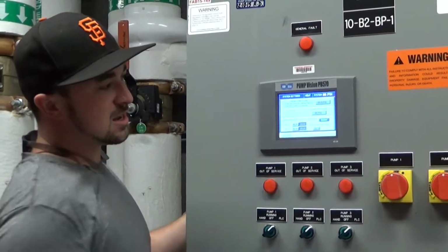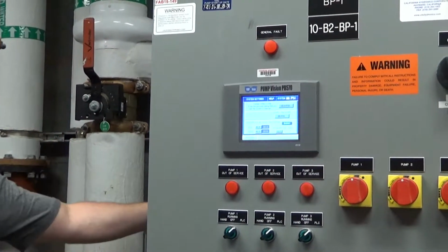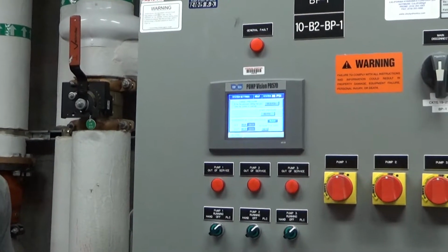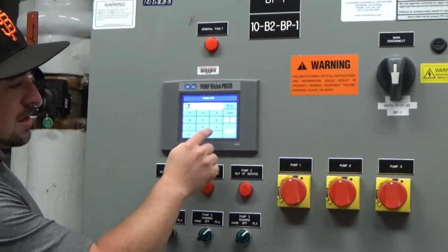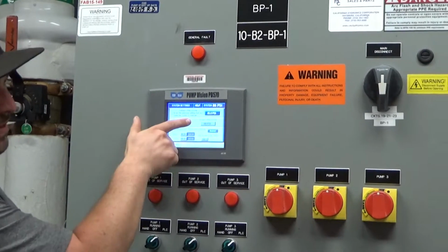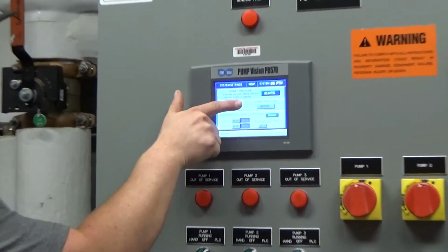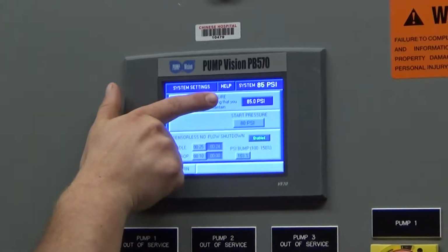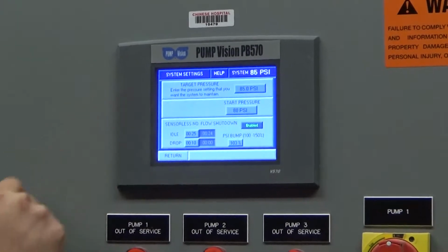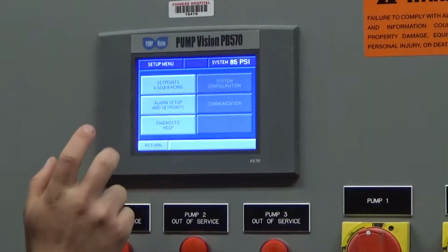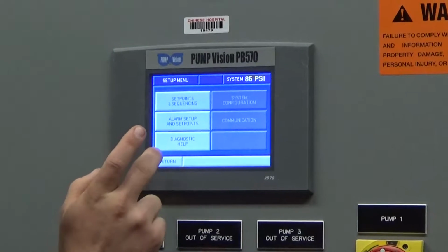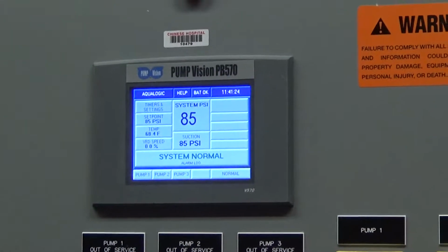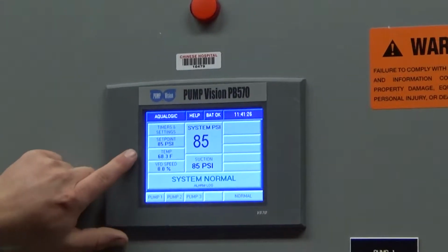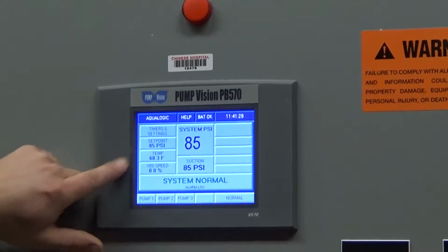But it is going to give you access to your set points. So say a year from now you decide, okay, we need 90 PSI at the roof. You click that, change that to 90, and then you would set your start pressure 5 PSI below that. So if I brought this to 90, I'd bring this to 85. You most likely will never have to do that, but we always want to show that. Also on here is your water temperature, which is nice.